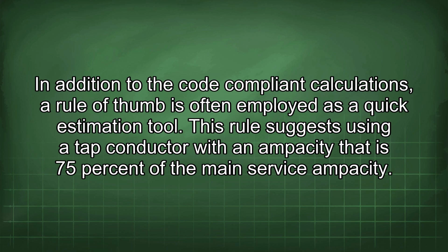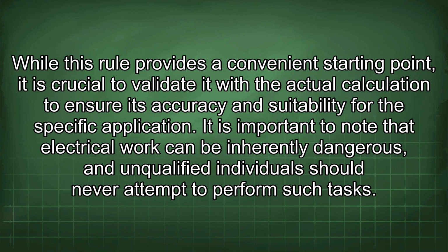In addition to the code-compliant calculations, a rule of thumb is often employed as a quick estimation tool. This rule suggests using a tap conductor with an ampacity that is 75% of the main service ampacity. While this rule provides a convenient starting point, it is crucial to validate it with the actual calculation to ensure its accuracy and suitability for the specific application.